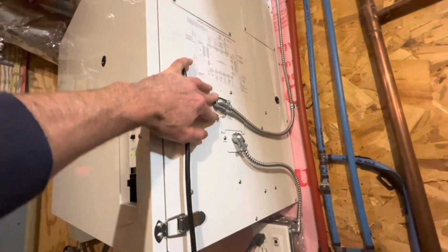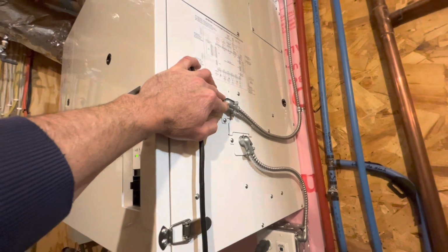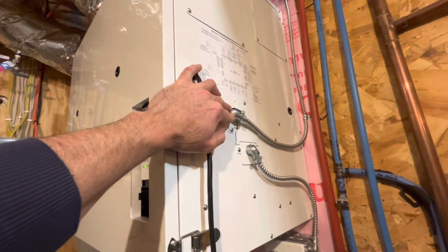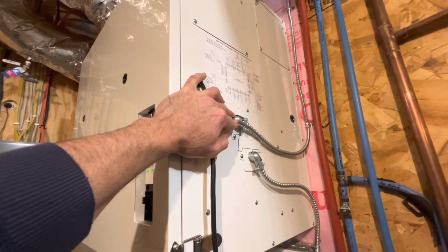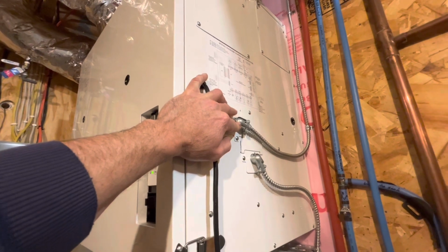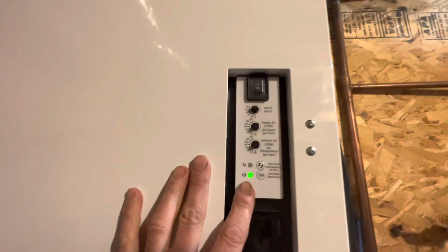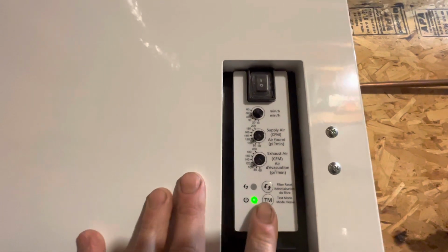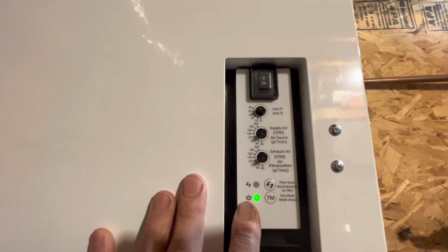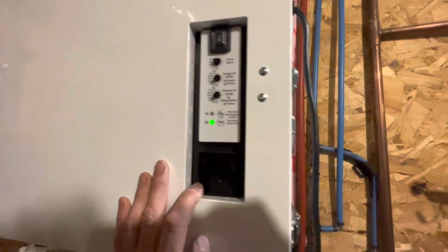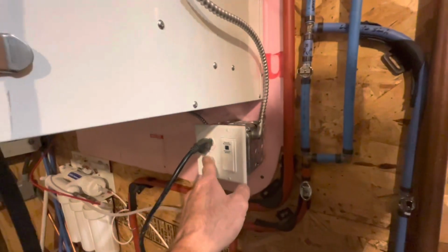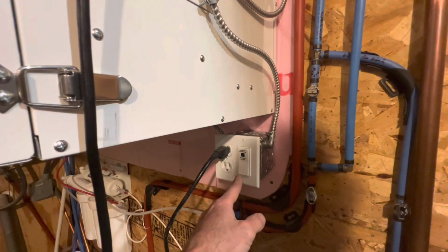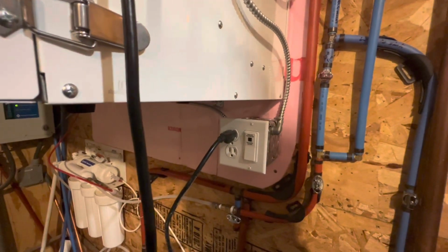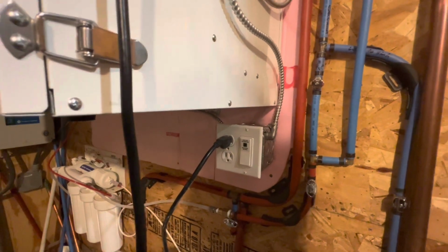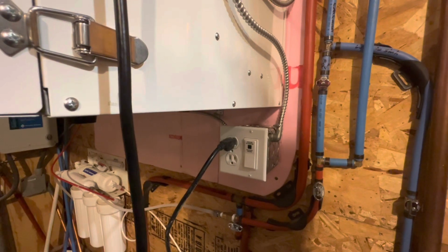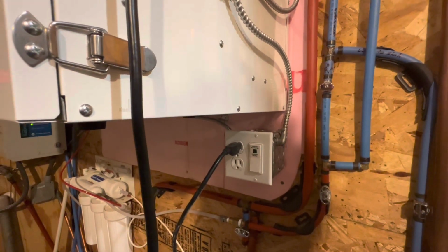This wire flex conduit here is going up to the wall mounted controller. I elected to buy the wall mount controller versus relying on these controls here, just dials for exhaust air, supply air, and minutes per hour runtime. So, like I said, for the wall switch, that's the manual wall switch. My thought there was I went with the Leviton Wi-Fi control wall switch. That way I could shut the unit off from my phone if I had a situation where I wanted to shut it off and I wasn't home.